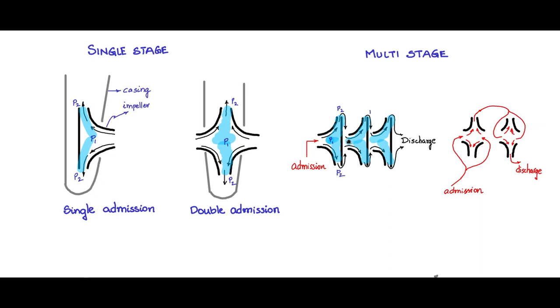In the multi-stage pump, pressures keep adding up. There is p1 and p2 at the first stage; p2 forces admission into the next stage at p3, then p4, and so on — the delta-p's keep adding up. In the double-admission case, p1, p2, p3 also add up. Because of this cumulative pressure addition, there is sufficient differential pressure from the first to the last stage to pump water to much greater heights. This is how multi-stage pumps work, generally used in submersible pumps for bore well applications.